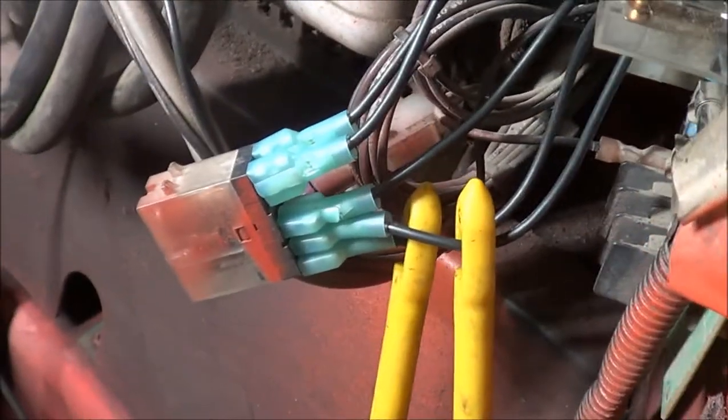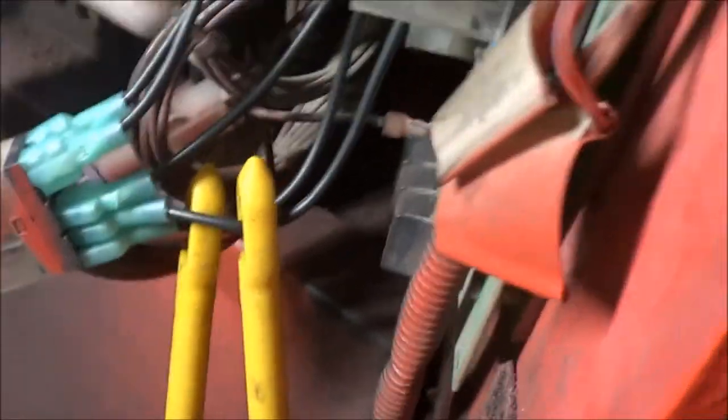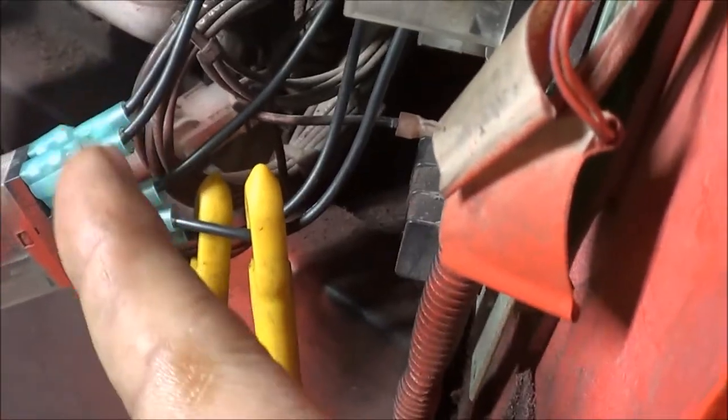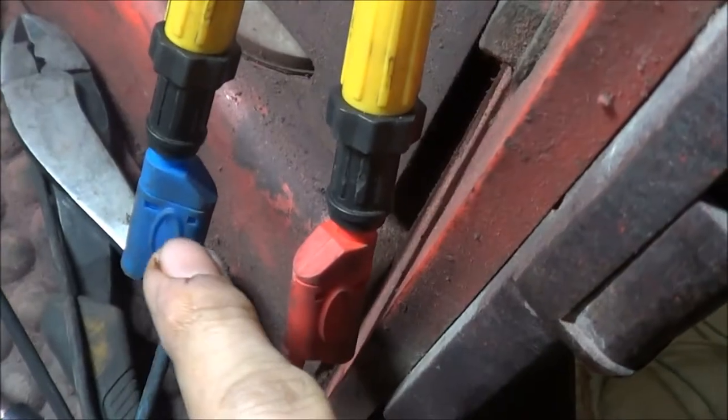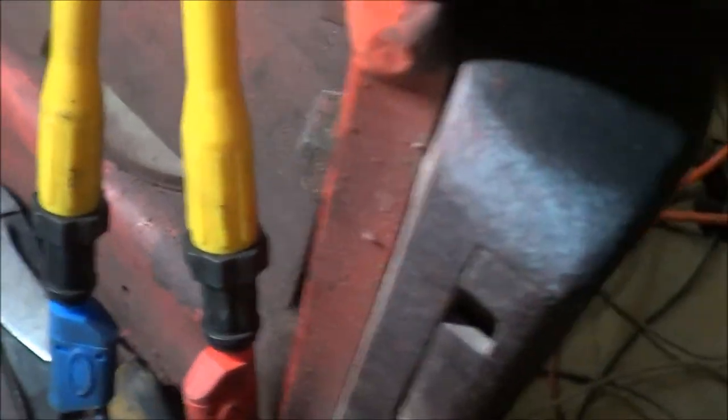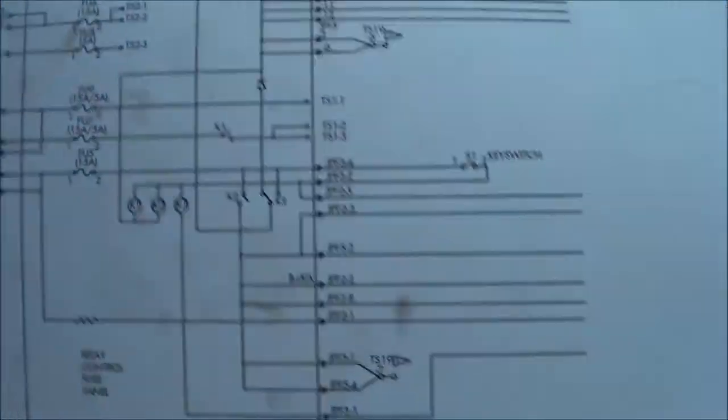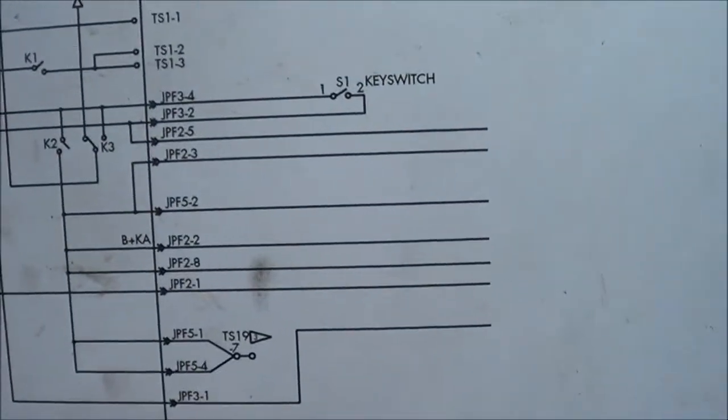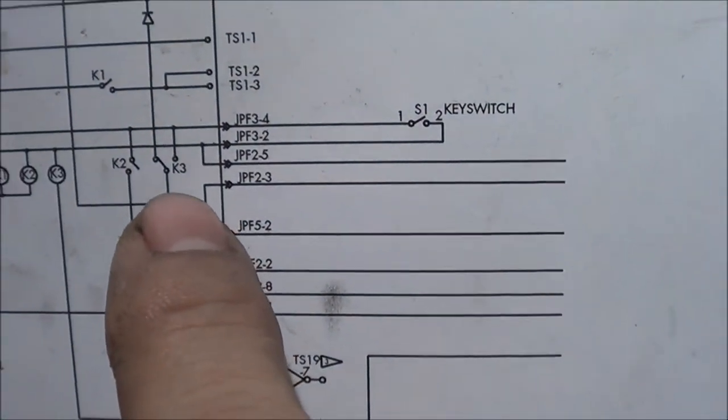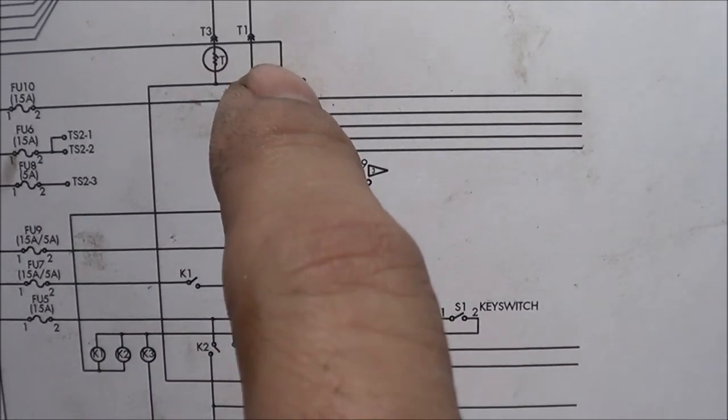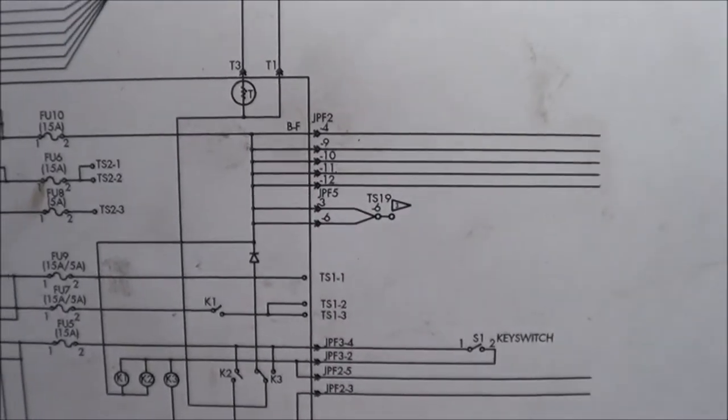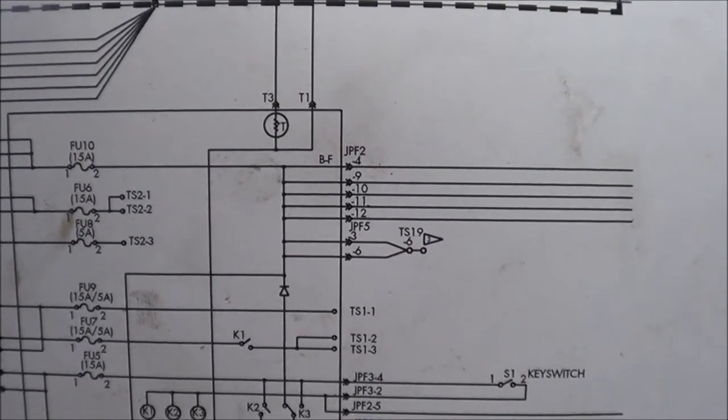Okay, so in order for us to test the relay K3, I had to adapt some cables into it and put the piercing probe on it. So my red trace is gonna be on the common and then my blue trace is gonna be on my normally open contact.